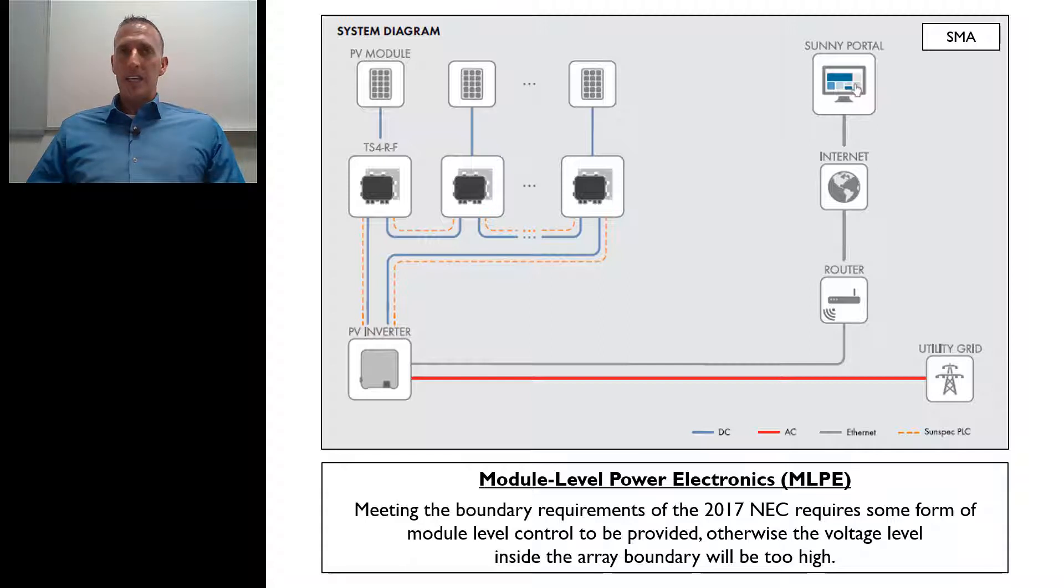The 2014 NEC allowed much higher voltage levels within the array boundary. The big change came when we went to 2017, and it said, hey, doesn't matter what your voltage level when the system's operating, within that array boundary, when the rapid shutdown is initiated, you've got to get down to 80 volts or less within 30 seconds.